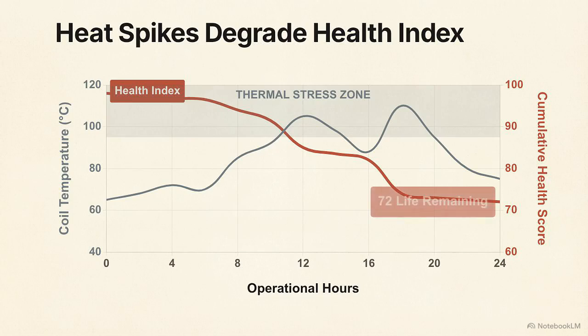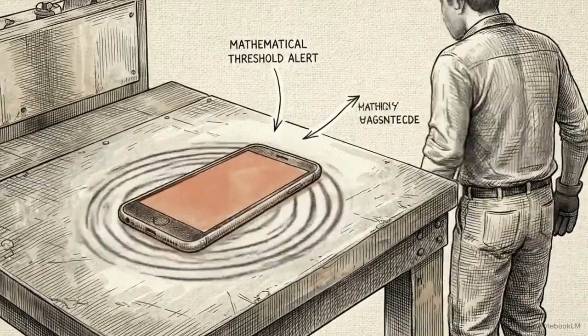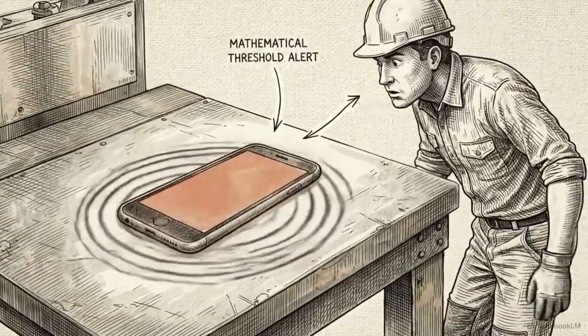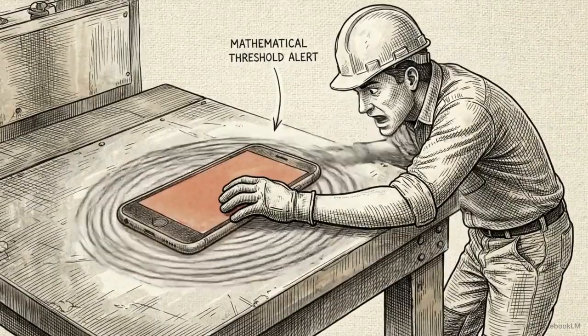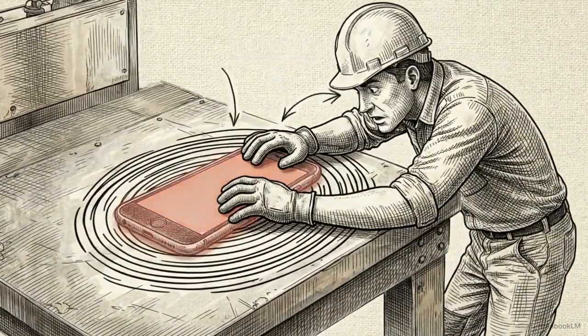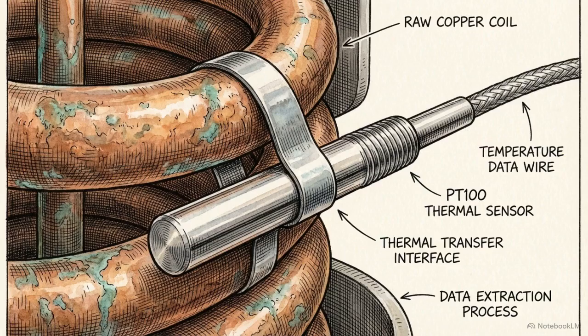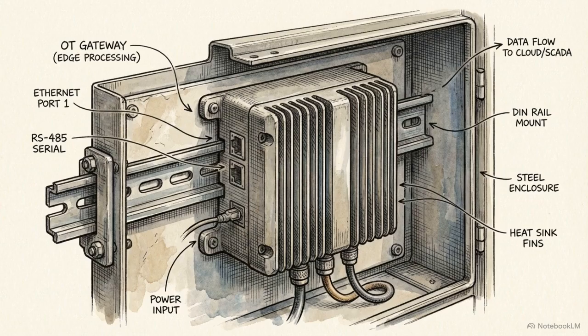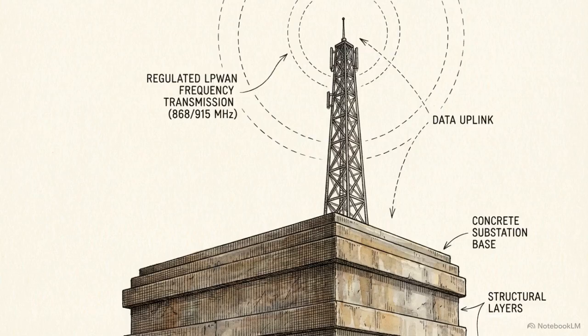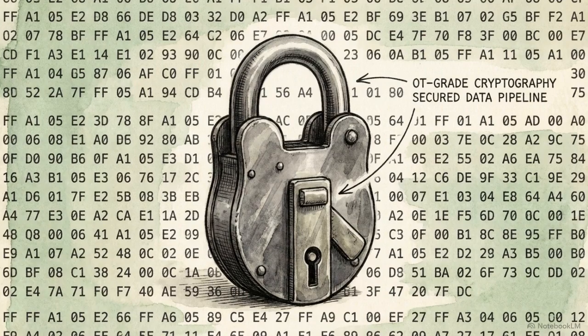The dashboard monitors the thermal curve against the health index. The moment the internal temperature crosses a pre-calculated mathematical threshold, the system automatically fires an alert to the engineering team days before insulation fails. By making the internal degradation of the transformer entirely visible, this continuous data pipeline effectively eliminates the temporal blind spot of the annual inspection. The predictive maintenance model extracts internal thermal data, pushing it through ruggedized edge gateways, transmitting it via regulated LPWAN frequencies, and securing it behind OT-grade cryptography.